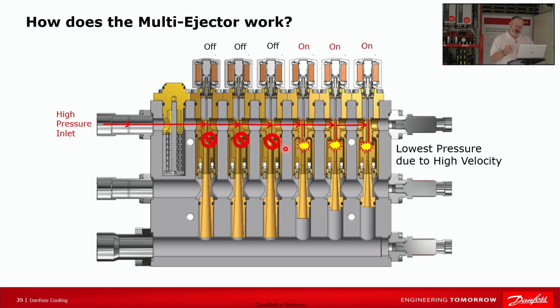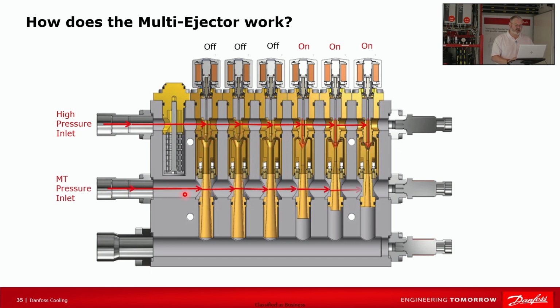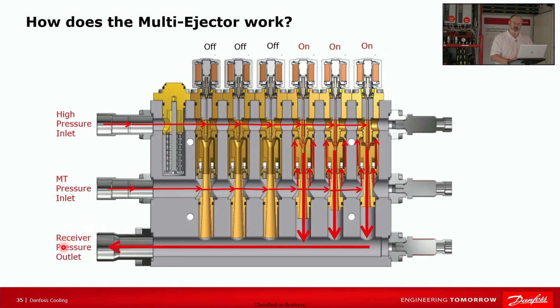So when we create that low pressure, we actually create a lower pressure than our medium temp suction at 400 pounds. And that's going to cause our medium temp return gas, which we've now piped back towards the ejector block, to draw into this. They call it lift. It's going to cause a lift to bring that, it's going to come into the ejector. It goes up here and mixes with the gas cooler. Then it goes through the mixing chamber and exits and all leaves together and goes back to the flash tank / receiver.